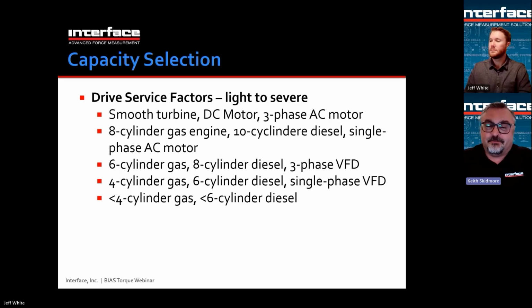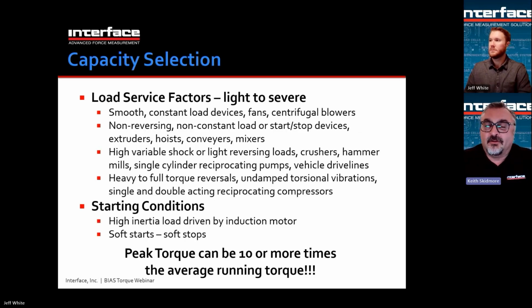And moving on, you also have a load service factor, which is the same idea, except it's about what is being driven by the system. That has a characteristic also. Again, a smooth thing like a fan or a blower is quite easy to spin. Something that's non-reversing like a conveyor or a mixer basically just keeps turning, maybe a little more difficult, but not terrible. Then you might have shock or reversing loads, crushers, hammer mills. Hammer mill sounds like a severe load. Single cylinder or reciprocating pumps, things that as you spin them get harder and easier to spin, create torque spikes in the driveline.